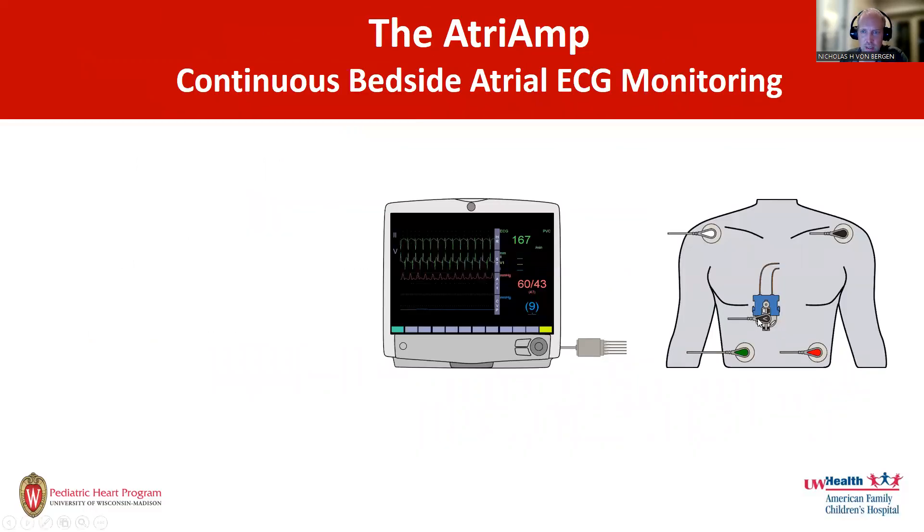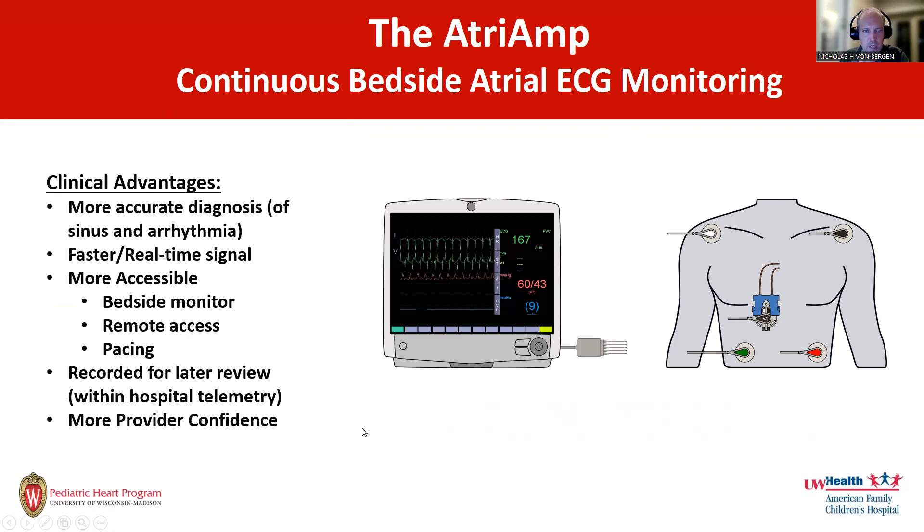The AtriAmp is this device that connects directly to the atrial epicardial wires, then allows us to hook to the precordial lead on the bedside monitor and allow continuous atrial electrogram monitoring on the bedside monitor. This has potential advantages: more accurate diagnosis of both sinus rhythms and arrhythmias. It's faster, it's a real-time signal, and it's more accessible — I can see the signals on the bedside monitor, or even at home. It also allows rapid connection for pacing if needed, and it uses the bedside monitor to record for later review.